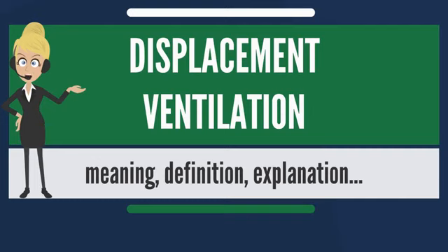By increasing the flow rate and the ability to remove greater thermal loads, the vertical temperature gradient can be reduced, but this could increase the risk of drafts. Pairing displacement ventilation with radiant chilled ceilings is an effort to mitigate this problem. According to some studies, displacement ventilation systems can only provide acceptable comfort if the corresponding cooling load is less than about 13 BTU/hr·ft² or 40 W/square meter.